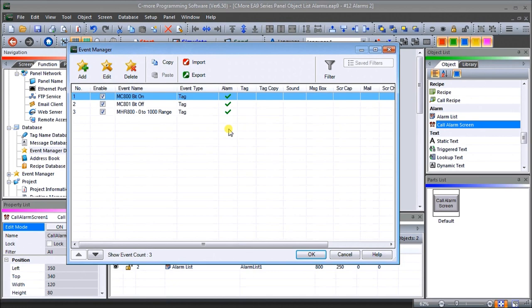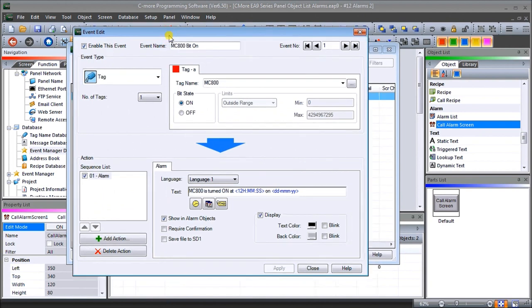If we click on the first alarm and hit 'edit', our event edit display comes up. The event name is 'MC800 bit on', which is our first alarm tag. The tag name is MC800, and the bit state is set to 'on' — so when this bit turns on, that's when we want our alarm to activate. When it activates it uses language one, and our text will say 'MC800 is turned on at', and then we give a time and date using the icons we can set.